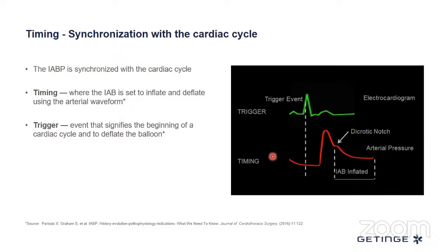You can do that, and the machine will run from there, but as soon as possible, connect the ECG, at least the right arm and left leg. And you can put it on the patient's back. I've seen people do this, especially if it's a fiber optic balloon itself.